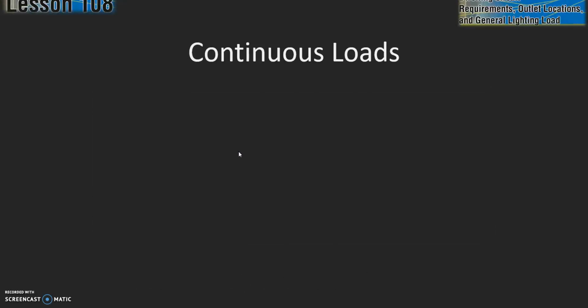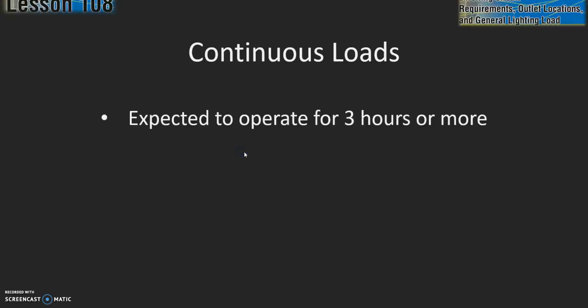Another important term, I don't know that they do such a good job explaining, but it is very important, is the term continuous load. The first thing we have to define, what is that? That's any load that's expected to operate for 3 hours or more. And I can tell you any of your HVAC, by definition, whether they're going to run for 3 hours or more, are considered continuous loads. And that's a term you're going to see a lot as well.